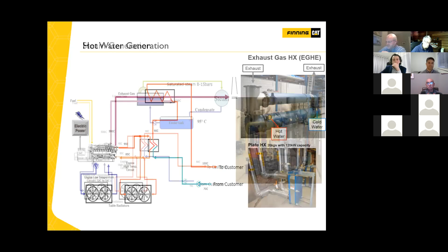Okay, now we want the steam. The layout for steam is similar, but as this is giving steam and hot water to the plant, same thing, coming out of the jacket water heat exchanger back to the engine, from the process side and back. So what we're seeing is again 500 degrees C exhaust gas going through the boiler. This accumulates steam at a pressure of between 8 and 15 bar, and that's 115 to 215 psi. So there are a few more safety considerations when we look at steam, but the concept is still fairly basic. I know good mechanical engineers that are probably falling asleep by now, but the process is very, very simple.